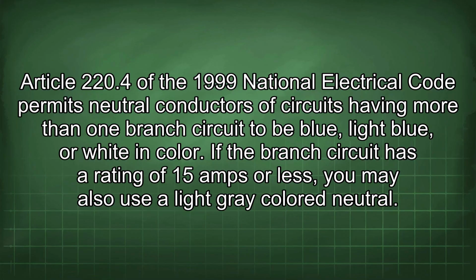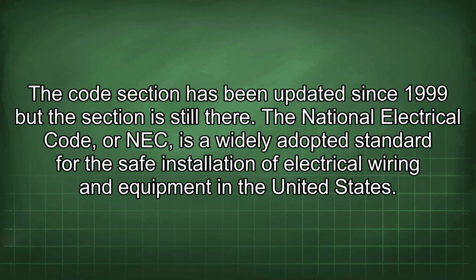Article 220.4 of the 1999 National Electrical Code permits neutral conductors of circuits having more than one branch circuit to be blue, light blue, or white in color. If the branch circuit has a rating of 15 amps or less, you may also use a light gray colored neutral. The code section has been updated since 1999, but the section is still there.